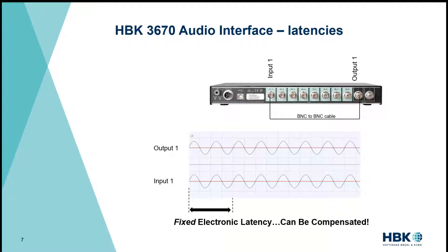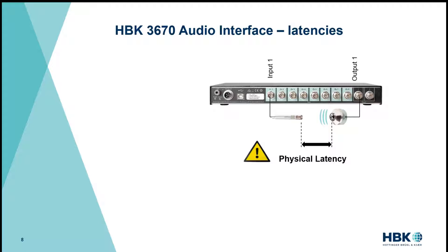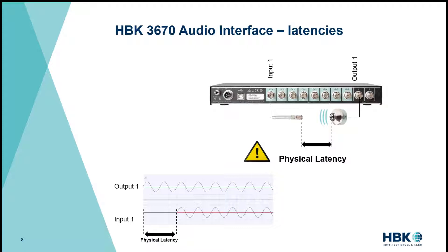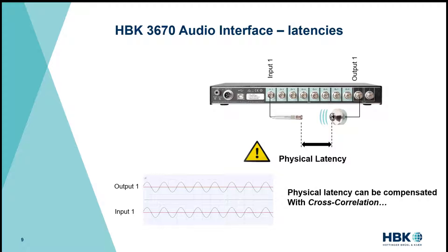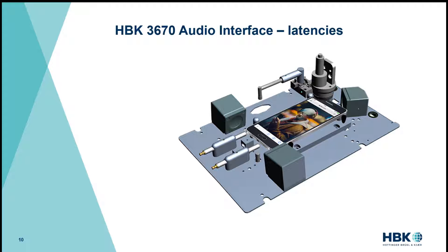There's another latency we have to take into account which is the physical latency between transducers. In this case it's a microphone in an artificial mouth, and due to the distance between the two transducers we have a physical latency that impacts synchronization. We can use cross-correlation techniques to estimate the time delay and compensate for it. In a quality control test station with fixed microphone and speaker locations, the physical latency is identical for all measurements, and since the 3670 has fixed electronic latency you can measure the total latency once and never calculate it again, saving precious processing time.